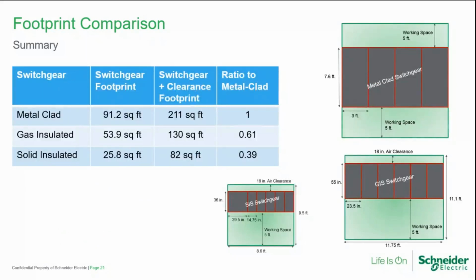So comparison between the 3, with that gas insulated switchgear being able to reduce by about 40%, and with the solid insulated switchgear being able to reduce that footprint by just over 60% compared to the traditional metal clad lineup. So a pretty big reduction in space. So that's a 15 kV example.